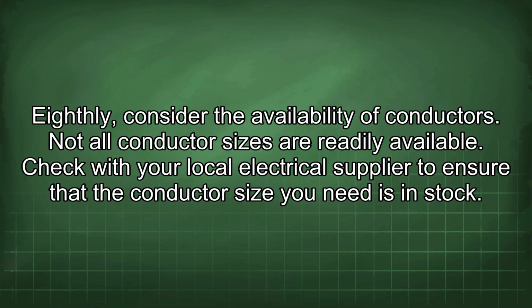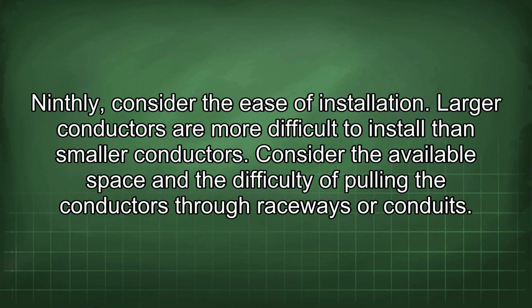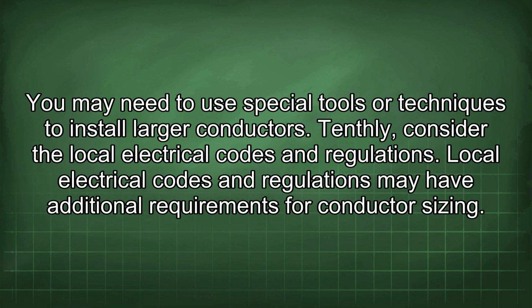Eighthly, consider the availability of conductors. Not all conductor sizes are readily available. Check with your local electrical supplier to ensure that the conductor size you need is in stock. Ninthly, consider the ease of installation. Larger conductors are more difficult to install than smaller conductors. Consider the available space and the difficulty of pulling the conductors through raceways or conduits. You may need to use special tools or techniques to install larger conductors.